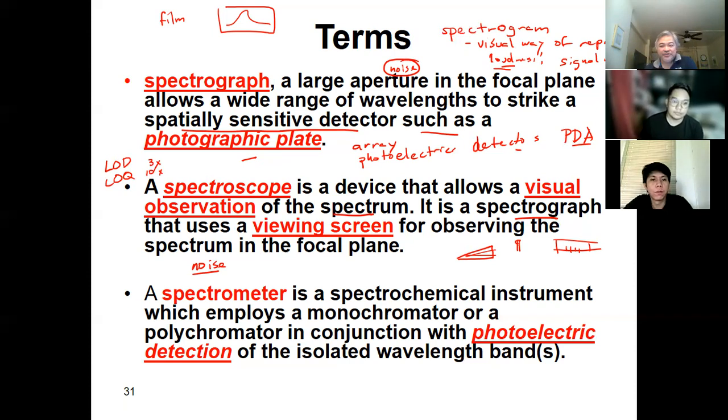Minsan problematic yung noise. Yung experience namin dito, in Raman, we always have this noise. I'm not sure, yung tinatawag namin cosmic rays. So nakakakuha usually siya ng cosmic rays. Now, how do we determine if it's a noise? If the signal is a noise or the signal is coming from your sample, how do you do that?